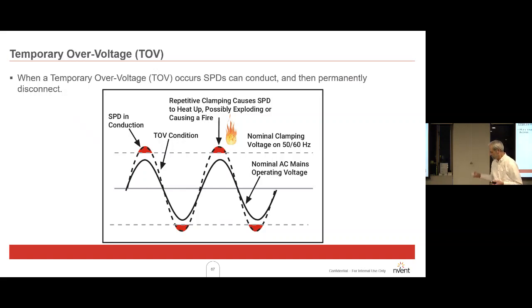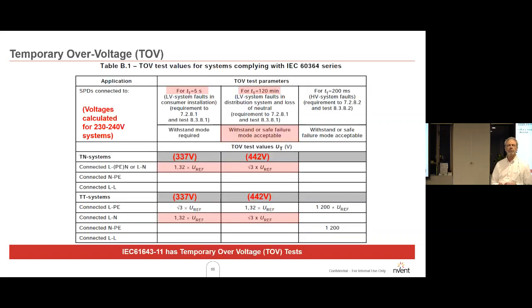This uses a technology which discriminates between the very short impulse time of a standard surge and the long time of a standard AC waveform, and it won't conduct the AC waveform, but it will still suppress the surge, conduct the surge. So that's a technology, transient discriminating technology, which can be used in those situations. They also mean the surge diverter can last longer because they're not consumed by little brief overvoltages.